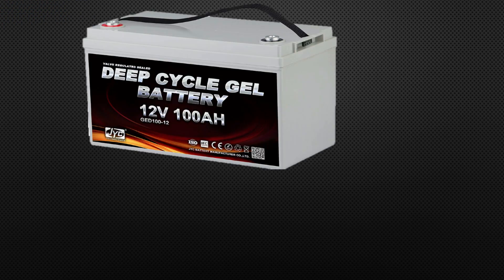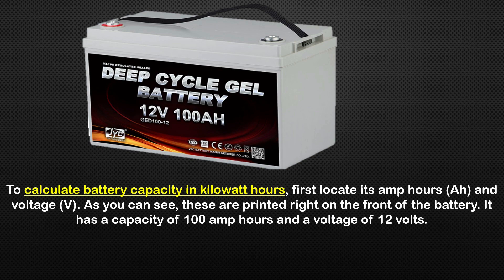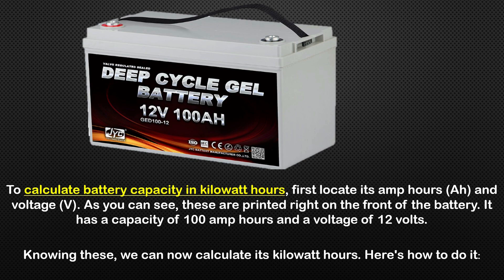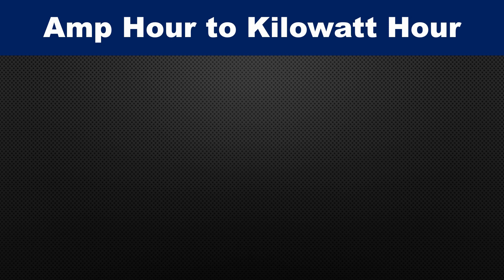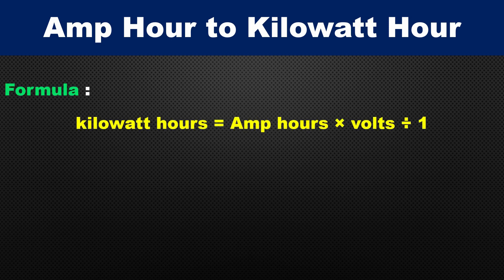For example, we have a battery whose ampere-hours is 100 AH and voltage is 12 volts. As you can see, these are printed right on the front of the battery — it has a capacity of 100 ampere-hours and a voltage of 12 volts. The formula for ampere-hours to kilowatt-hours is: kilowatt-hours equals ampere-hours multiplied by volts divided by 1000.